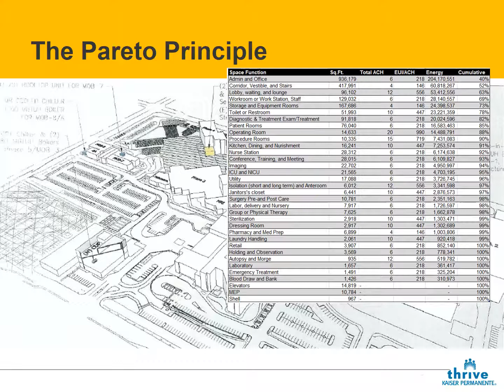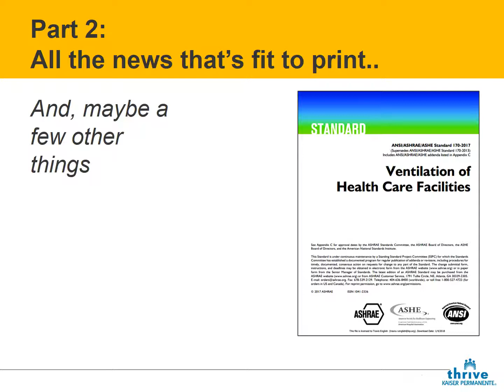Toilet rooms are going to be unoccupied. Even if you assume that toilet rooms are occupied 4 hours a day, that means they're empty 20 hours a day. And so ventilating those all the time, if you move that into units of cubic feet per year, then you get it, right? There's a ton of energy that just goes out. So that's how we're going to do it. I believe the solution here is basic blocking and tackling.